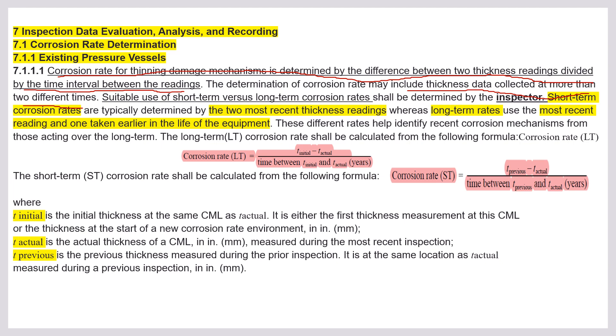The determination of corrosion rate may include thickness data collected at more than two different times. The suitable use of short-term versus long-term corrosion rates shall be determined by the inspector. Short-term and long-term rates apply only to pressure vessels. For API 653, there is no short-term and long-term — only one rate. Here in pressure vessels we have both short-term and long-term.